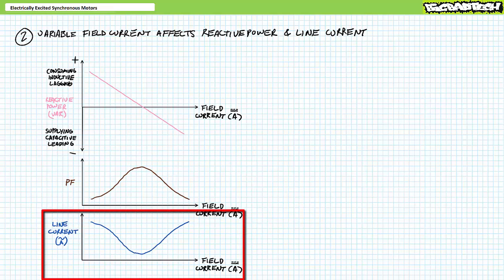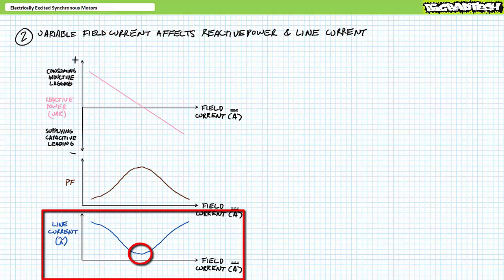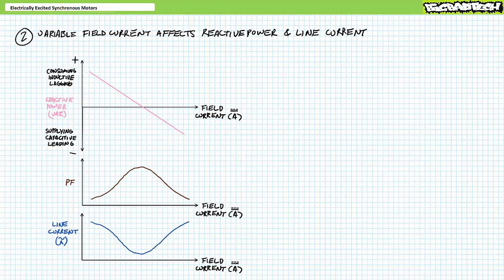A graph of line current as a function of field current for a given load condition looks something like this. At low levels of rotor excitation, the synchronous motor draws large amounts of lagging current, accounting for both the real and positive reactive power components. If field current increases, it draws less reactive power, thus current magnitude and phase shift decrease. When field current is adjusted such that the synchronous motor neither draws nor supplies reactive power, current bottoms out and is perfectly in phase with voltage. As field current is further increased, the synchronous motor starts supplying increasing amounts of negative reactive power, thus current magnitude increases and phase shift increases in a leading fashion. The graphs of power factor and line current magnitude as a function of field current are essentially inverses of one another. Note that a DC overbar is used for field current, emphasizing the rotor draws DC, while an AC overbar is used for line current, emphasizing the stator draws AC. Do not expect these helpful reminders in a field or lab environment.